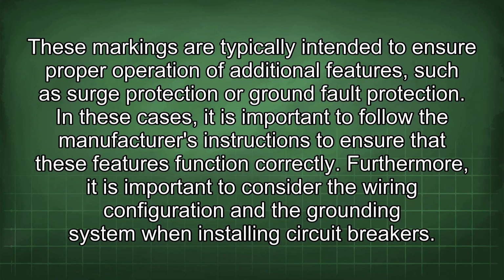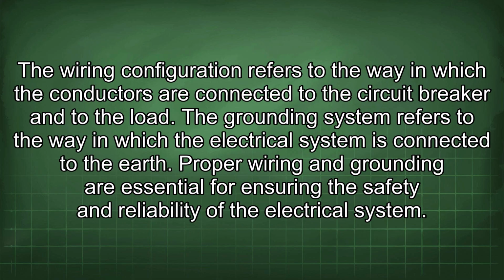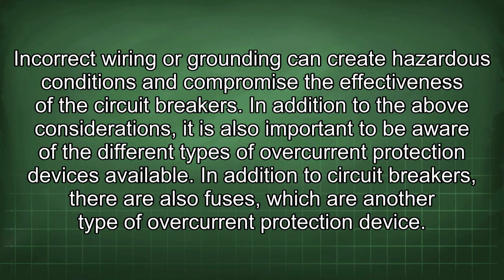Furthermore, it is important to consider the wiring configuration and the grounding system when installing circuit breakers. The wiring configuration refers to the way in which the conductors are connected to the circuit breaker and to the load. The grounding system refers to the way in which the electrical system is connected to the earth. Proper wiring and grounding are essential for ensuring the safety and reliability of the electrical system. Incorrect wiring or grounding can create hazardous conditions and compromise the effectiveness of the circuit breakers. In addition to the above considerations, it is also important to be aware of the different types of overcurrent protection devices available. In addition to circuit breakers, there are also fuses, which are another type of overcurrent protection device.